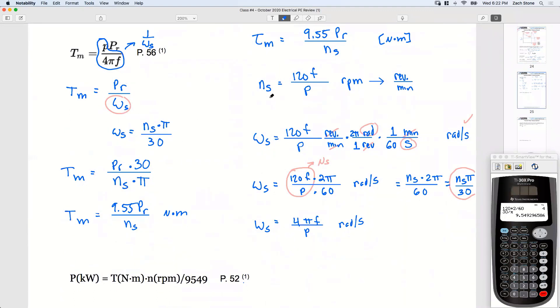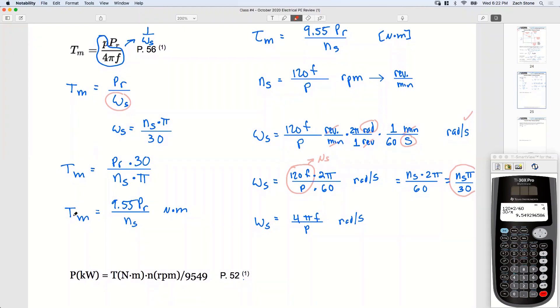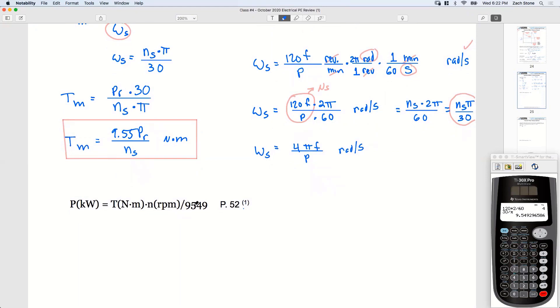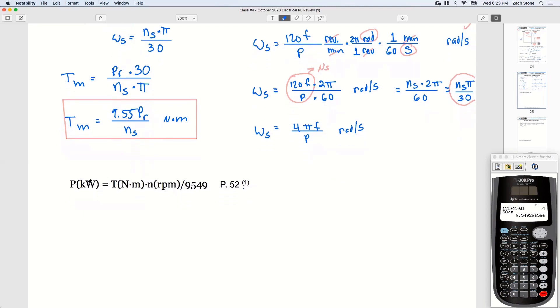Sometimes you're given N_s and need to find poles, or vice versa — that's really the only extra step. Now for the next formula on page 52: be careful, because the notation uses parentheses to indicate units, which can look like multiplication. Power is in kW, torque in newton-meters, and speed in RPM. It's the same formula we've been using — just watch out for that notation.